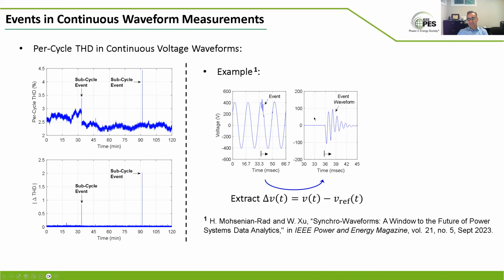So superposition of this event waveform on top of the regular 60 hertz signal, in this case, makes for the real waveform. And getting these waveforms may allow you to find patterns. For example, these are event waveforms. Maybe these inverters, when they switch, when they operate, create these sort of waveforms. You could get pattern recognition. You can use clustering techniques to look at these sorts of problems. If you have it only on 1 or 2 inverters, no big deal. But if a lot of inverters in your system have this issue together, that could affect your power quality on the grid or could initiate other stuff.